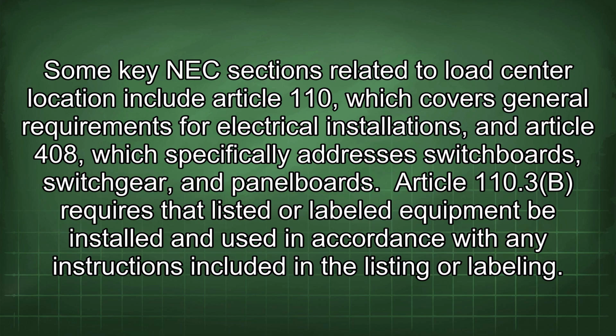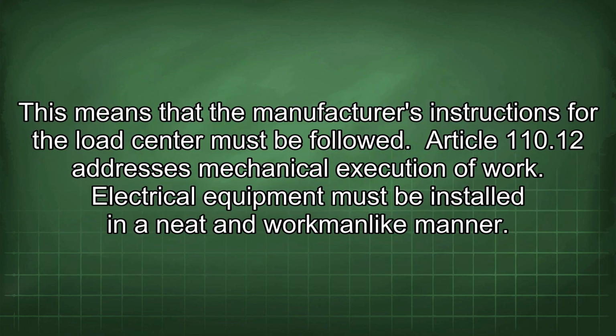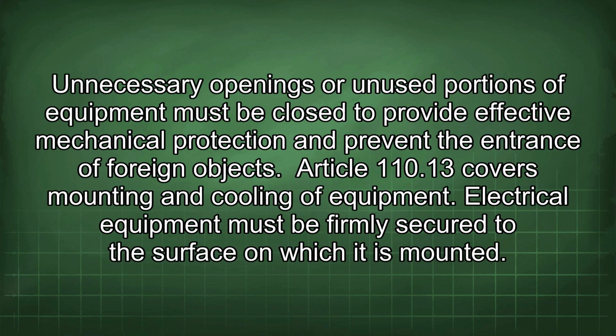Article 110.3(B) requires that listed or labeled equipment be installed and used in accordance with any instructions included in the listing or labeling. This means that the manufacturer's instructions for the load center must be followed. Article 110.12 addresses mechanical execution of work. Electrical equipment must be installed in a neat and workmanlike manner.